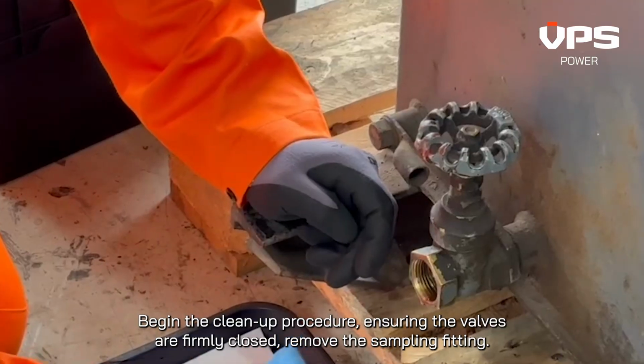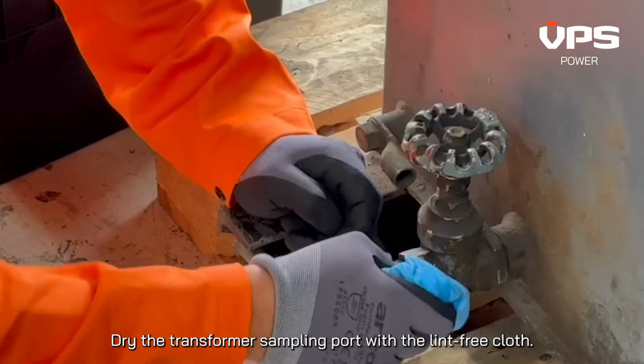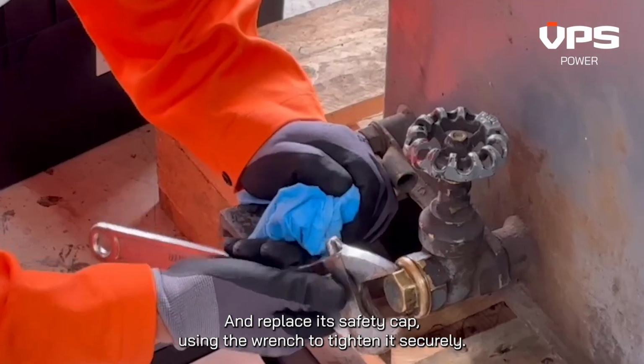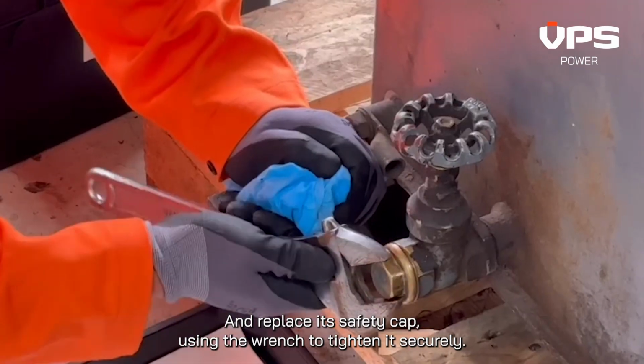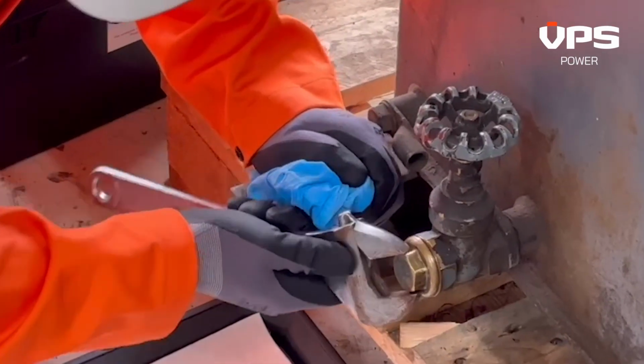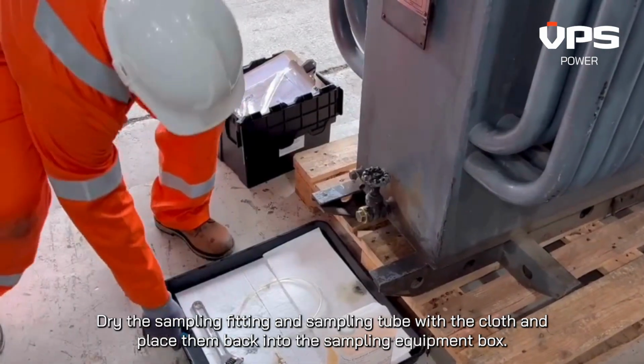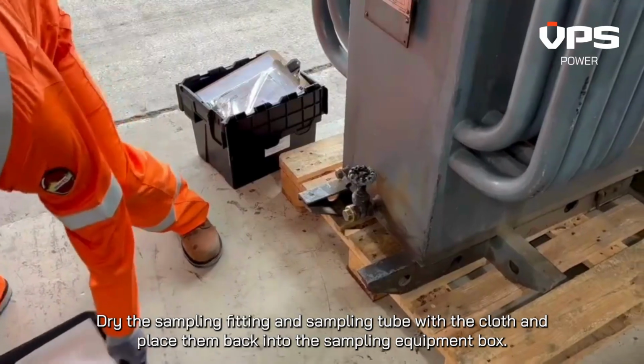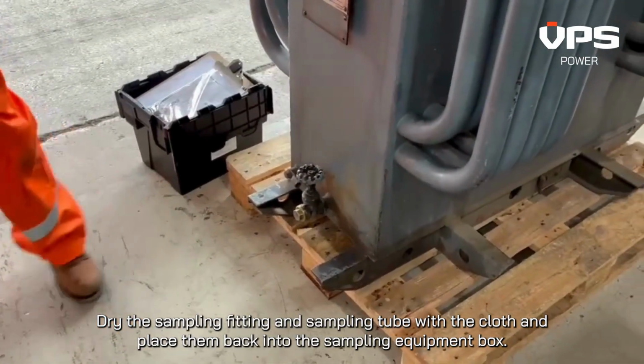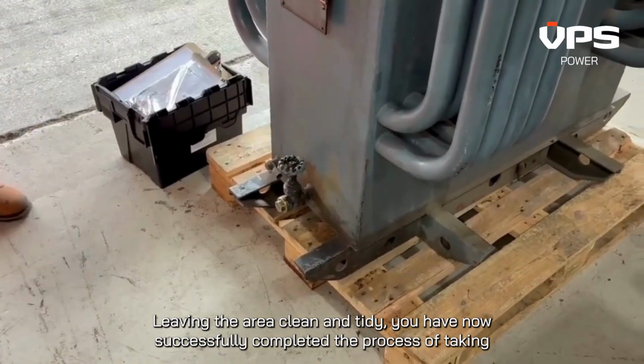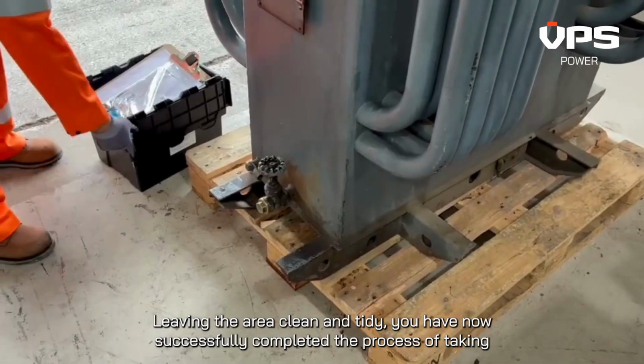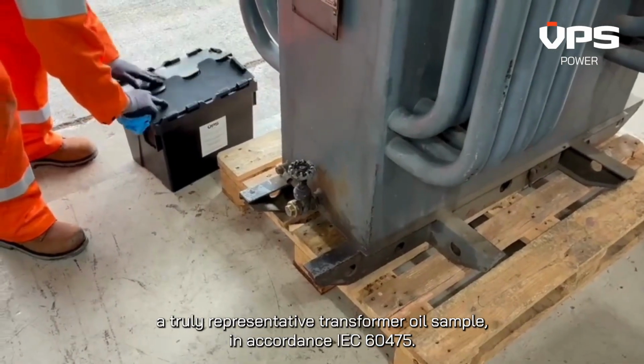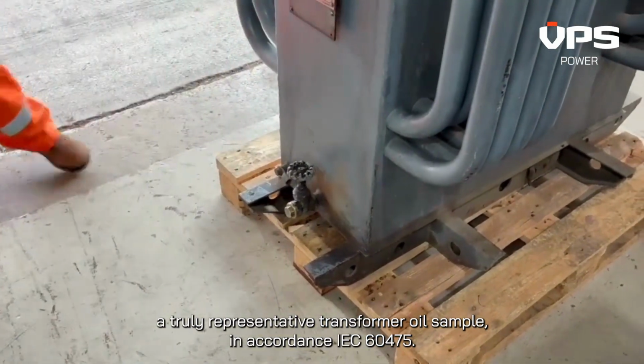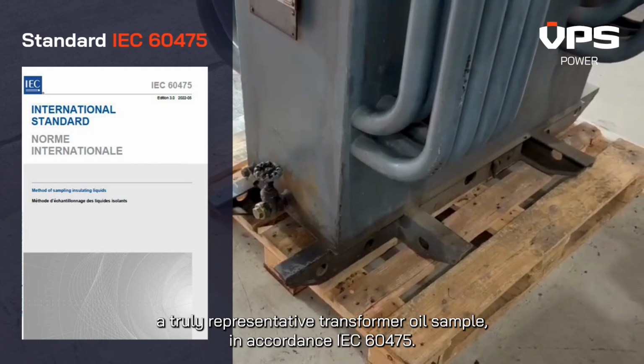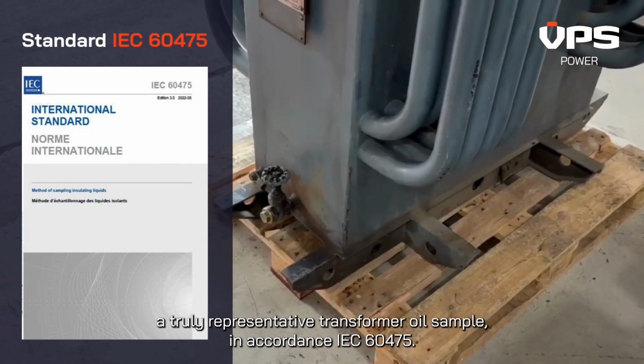Remove the sampling fitting. Dry the transformer sampling port with a lint-free cloth and replace its safety cap using the wrench to tighten it securely. Dry the sampling fitting and sampling tube with the cloth and place them back into the sampling equipment box. Leaving the area clean and tidy, you have now successfully completed the process of taking a truly representative transformer oil sample in accordance with IEC 60475.